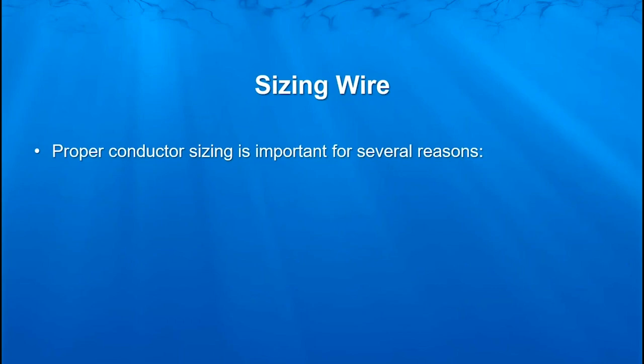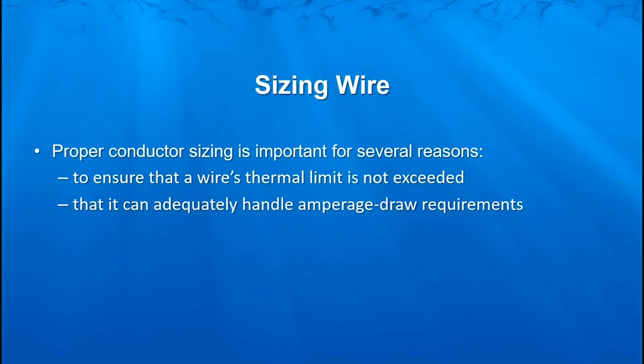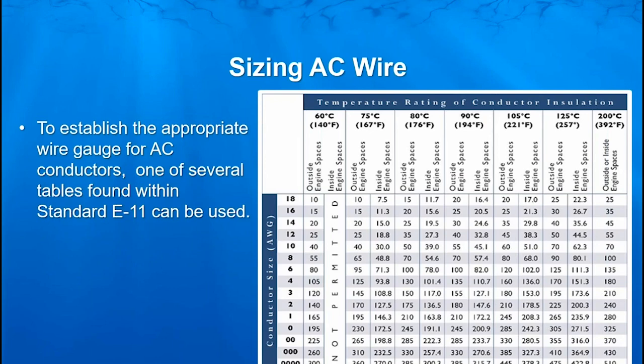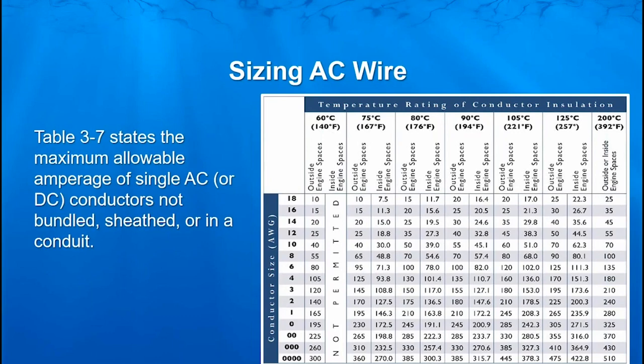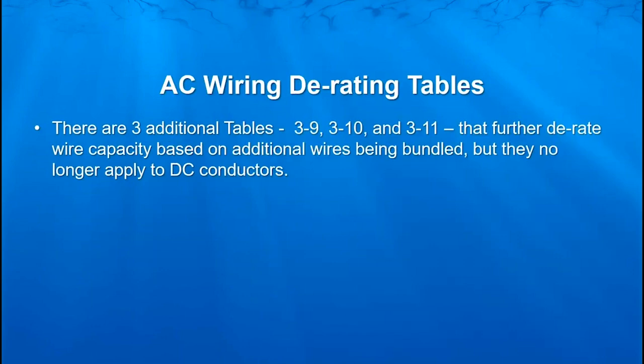Proper conductor sizing is important for several reasons. We need to ensure that we're not going to exceed the wire's thermal limit that it's rated for, that it can adequately handle the amperage draw requirement. And for DC conductors, that the wire does not exceed the voltage drop limits prescribed in standard E11. In sizing AC wire, we're going to use one of several tables found within standard E11. Table 3-7 gives us the maximum allowable amperage of a single AC — and in this case also DC — conductor that is not bundled, sheathed, or in a conduit. Table 3-8 gives us allowable amperages when we have up to three current-carrying conductors that are bundled, sheathed, or in a conduit.